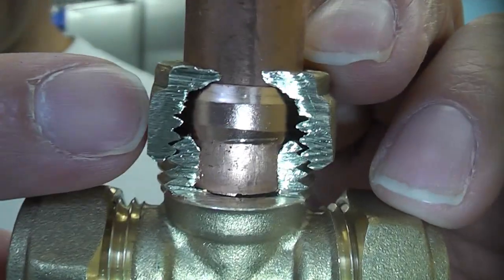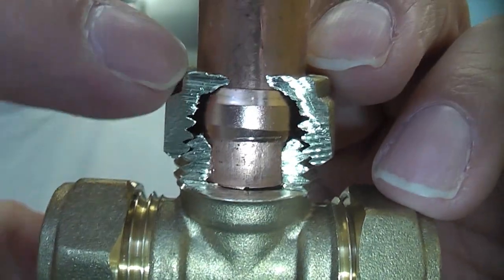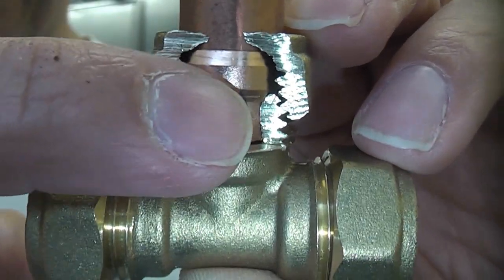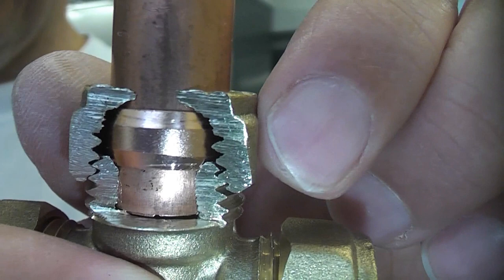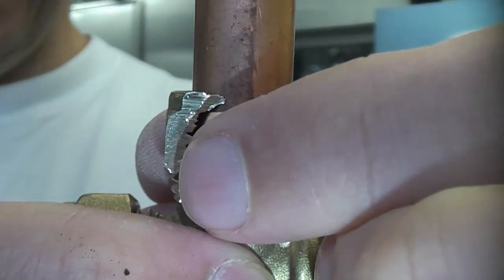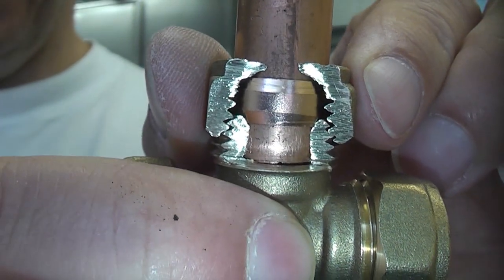I've actually cut parts of this fitting away so you can see how it works. You can see that the actual olive is being gripped at the top there by the nut, which is forcing the olive down into the seat and compressing it. Once you get to a certain tightness it will actually compress the olive onto the pipe and also seal the space in the joint, making a watertight joint.